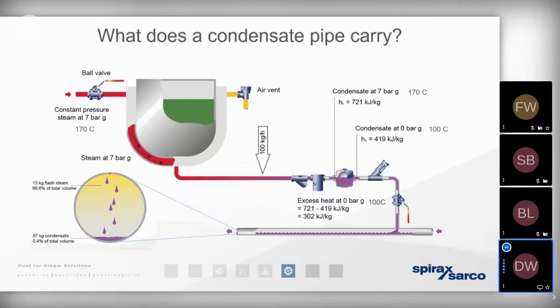But the problem we have is understanding that the behavior of the condensate when it moves across the steam trap means that there is going to be a pressure drop. We need to have that pressure drop. We need a good motive energy upstream of the steam trap so the steam can push the condensate away so it can travel back to the boiler house under its own motive energy.